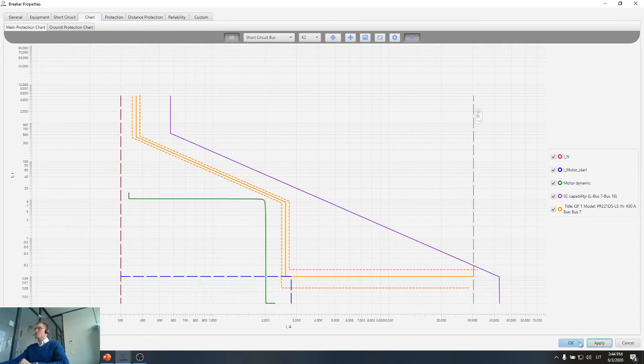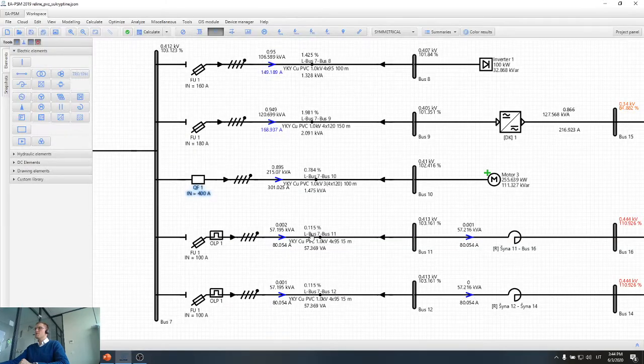As I have mentioned, don't use fuses for the motor protection. Motor breakers or a normal circuit breaker should be used in order to avoid unsymmetrical voltage for our motor.